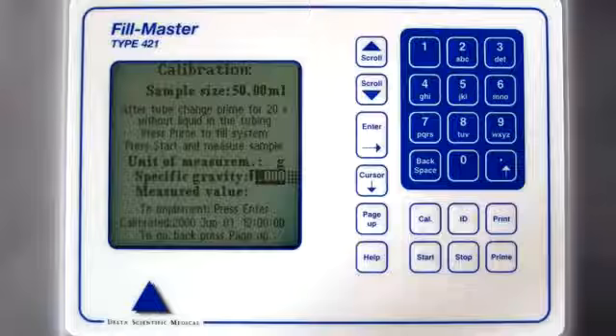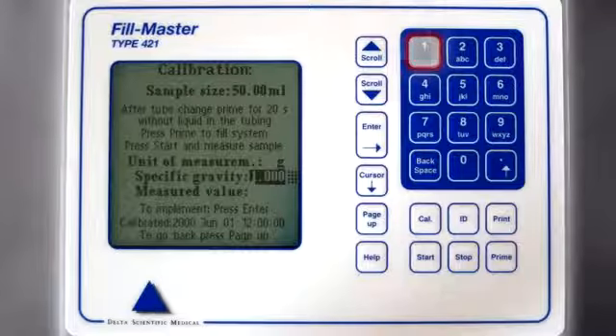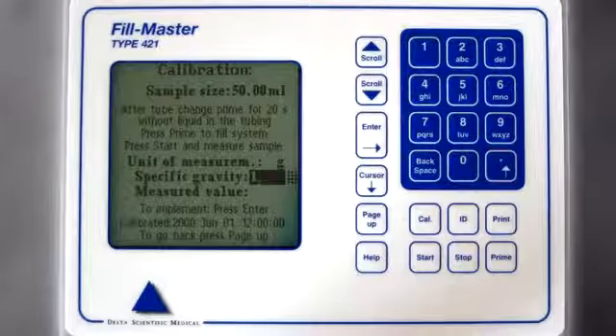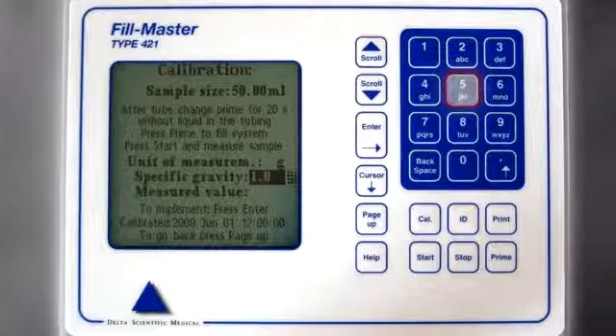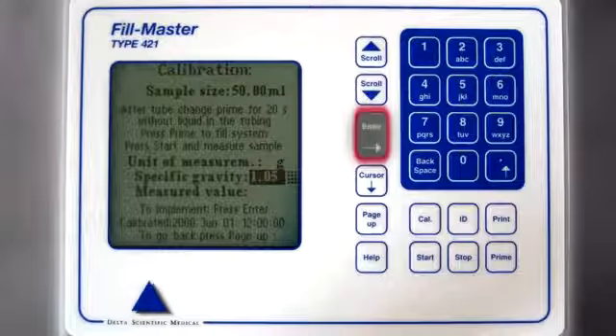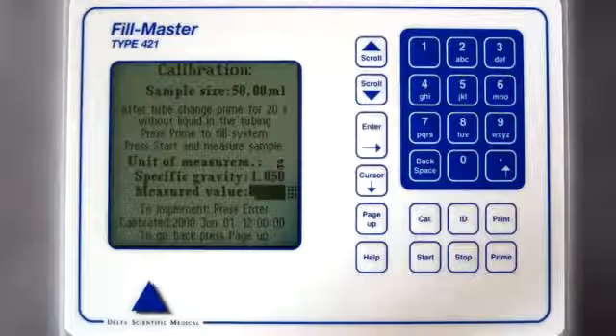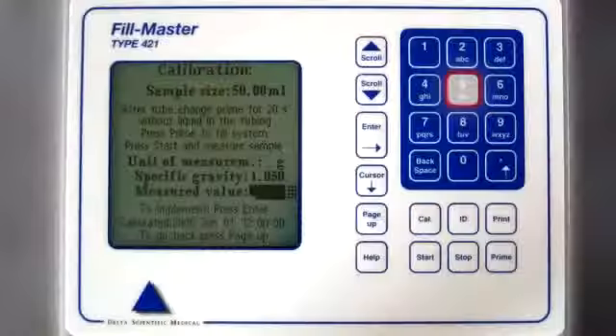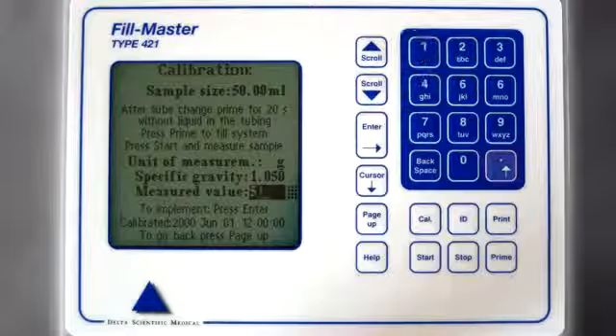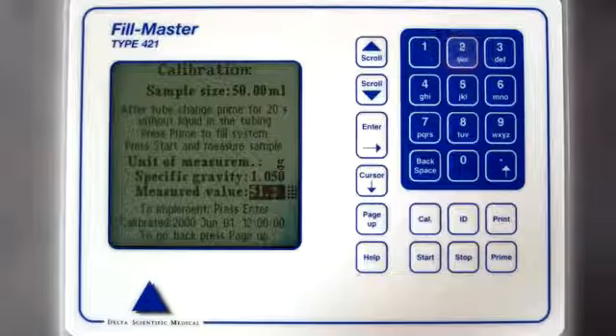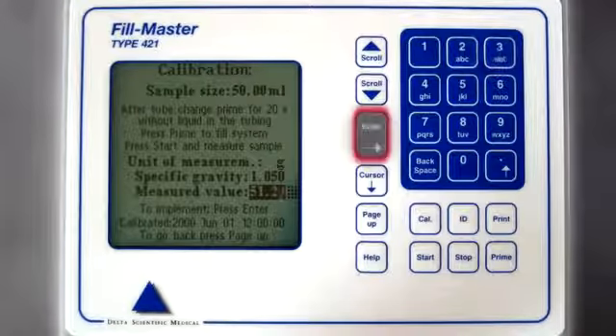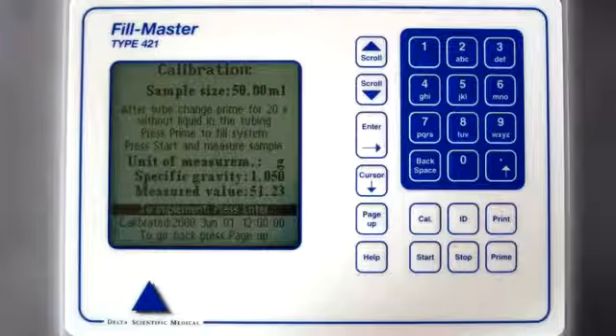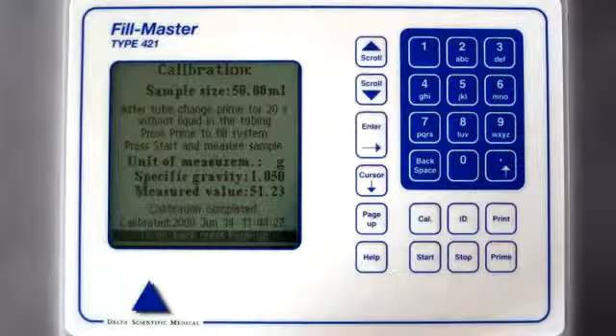When you have chosen grams or milligrams, you need to inform the pump about the specific gravity of the liquid in question so that it can convert weight to volume. Thus you key in the specific gravity on the keyboard and press Enter. The cursor will now be in the measured value line. Use the keyboard to key in your measurement result. And press Enter. A new line will now appear saying, to implement, press Enter. After doing that, a line will tell you that calibration is completed and give you the date and time in a line below.